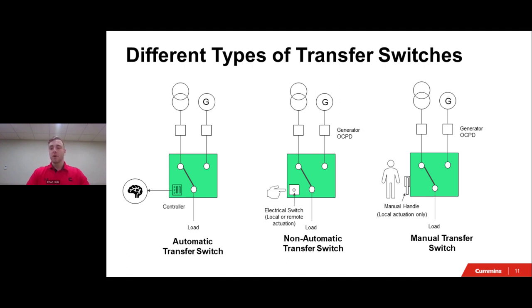And then lastly, off to the far right there with the little guy standing next to the transfer switch is our manual transfer switches. These switches can be operated to switch between power sources at any given time. While this surely simplifies the design, it is important to recognize that manual transfer switches typically are not equipped with devices to monitor the acceptability of voltage, frequency, or phase angle differences on the alternating current circuits that they connect.